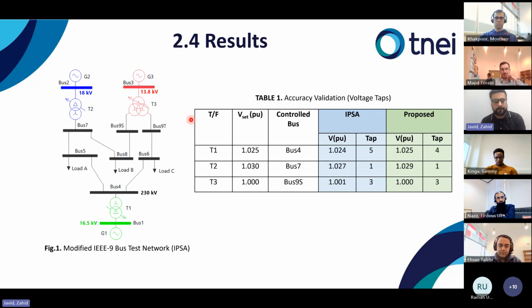Here is the accuracy validation we have done for the tap positions in this network. This is the modified IEEE 9 bus network. There are three voltage regulators, T1, T2, T3, and one of them is a three winding transformer voltage regulator, which we have modeled as well, and we have published on how to model a three winding transformer voltage regulator in the load flow formulation. I will share that resource at the end of this presentation. There is a set voltage for each regulator, and then a control bus, and we compare the results with IPSA. IPSA is the TNEI flagship software used for power system analysis. There is only one tap position difference at T1, but with the proposed model, even the voltages are close to the set value. So we tested this with the IPSA software, and we found that the accuracy of the proposed solver is good.